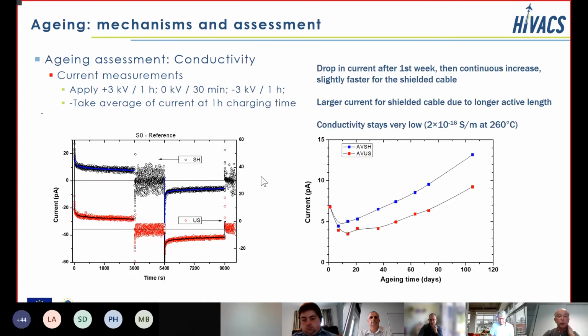Regarding conductivity measurements, we did them with 3 kilovolts applied to the cables, and here are the results for the current as a function of aging time. All measurements were achieved at 260 degrees, PD or DC current, and we can see a slight increase of the current by a factor of roughly 2 or even less, and no significant difference between shielded and unshielded cables. So those are quite reproducible results, and we still have a very low conductivity even after 4 months of aging.